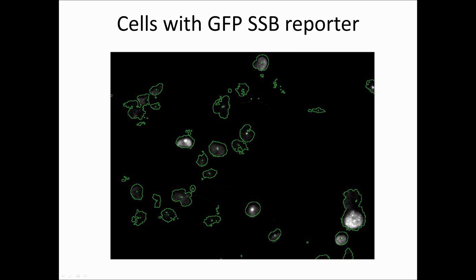So this is a picture of some cells which were located, these are ones that express GFP. In fact, this is the system that Alan will demonstrate to you this afternoon. So what we've done here is use the diffuse GFP which is within this cell to locate the nucleus of the cell. And we find the center of gravity of the cell and that's what these little green X's are. That's where we're intending to shoot. And then where the focal point, focus comes up is where we actually shot. And you see we're, a good registration of that. So this is normally, or most often we do experiments where the cells are stained with Hoechst, which gives a much brighter signal than this GFP does. But this is adequate for finding. And it's a good demonstration that if they're, we're hitting where we claim we want to.